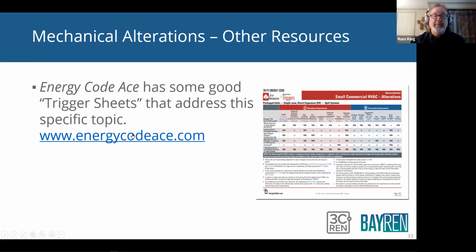There's a really nice summary that Energy Code ACE puts out. It's called the Energy Code ACE Trigger Sheet for Small Commercial HVAC Alterations. It has this really nice little grid where there's a description of what you're doing, and across the top, it shows whether or not you have to meet those requirements. One of these, again, duct sealing and testing, is at the end here, okay? So if you're doing these things, here's whether or not you have to do the duct leakage testing. There's a whole bunch of other stuff in here about controls and ventilation and economizers and stuff like that. So this is a really handy little document. Be sure to get your hands on that. Go to Energy Code ACE and it's in the tools section, okay?